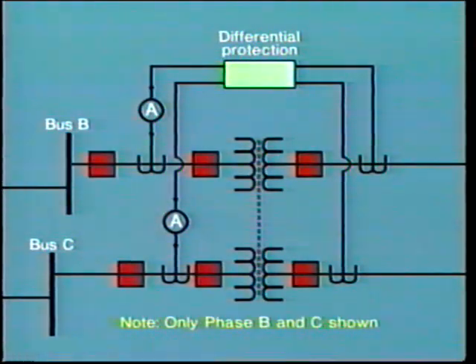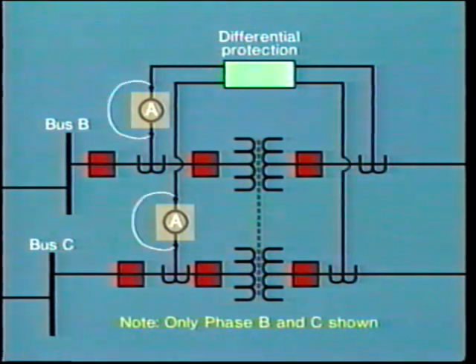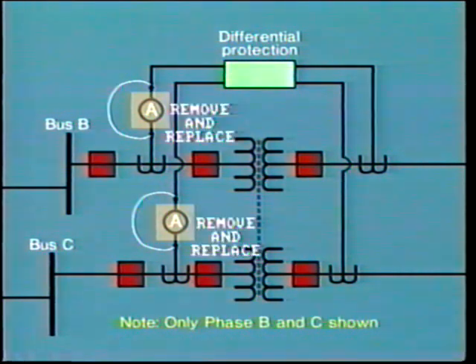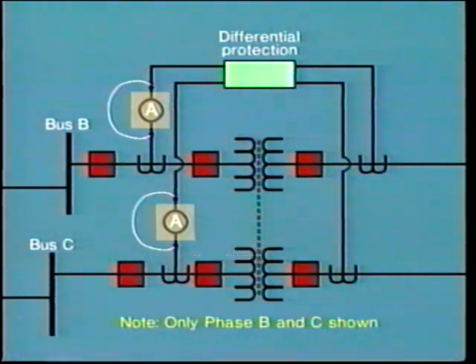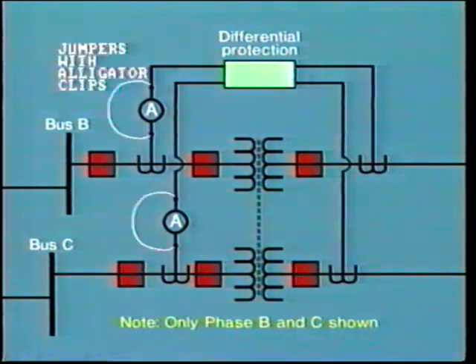And here is another interesting case. 2 technicians were involved in replacing 2 ammeters on a live transformer. Each ammeter formed part of the differential protection circuit. The objective was to bypass the ammeters with jumpers, remove and replace the ammeters, and then remove the jumpers. Jumpers with alligator clips were used.